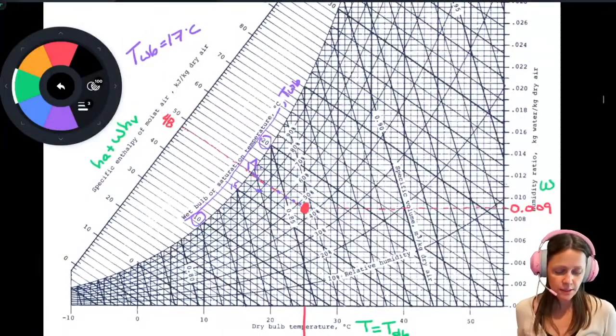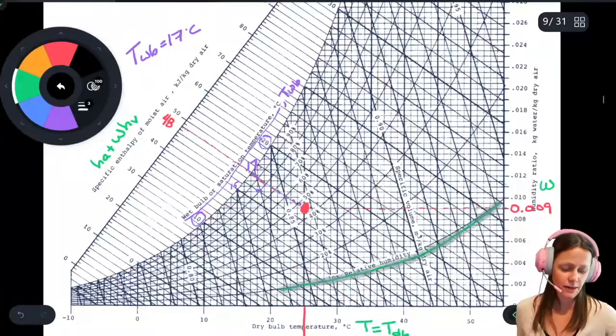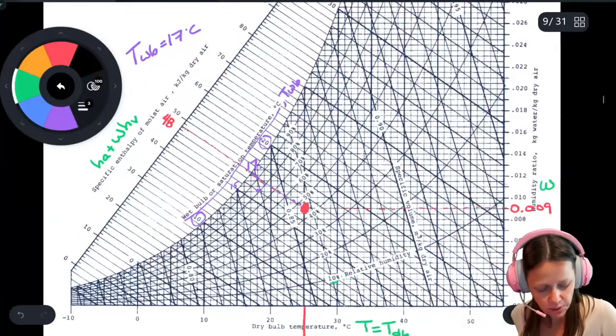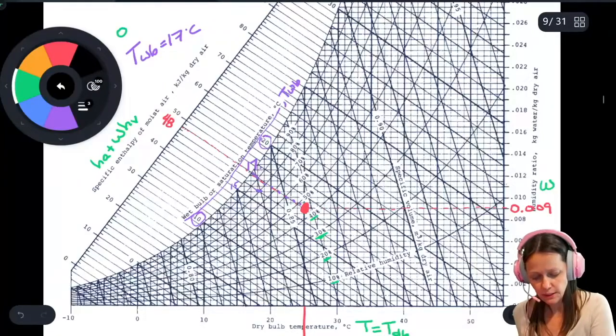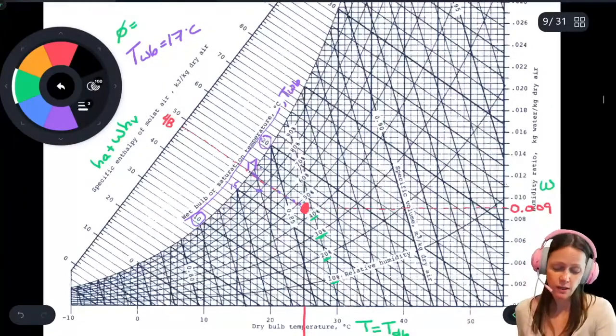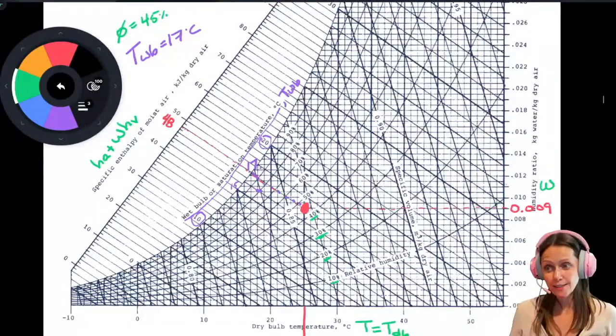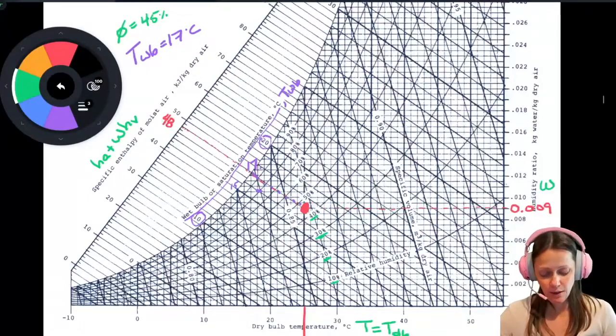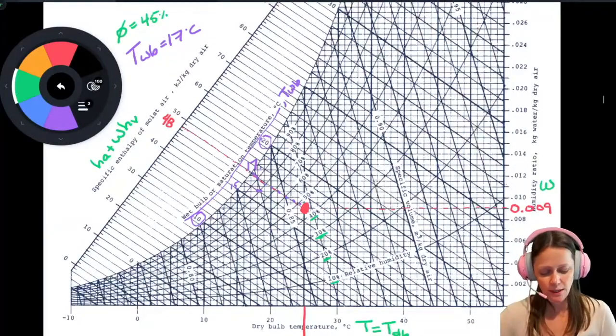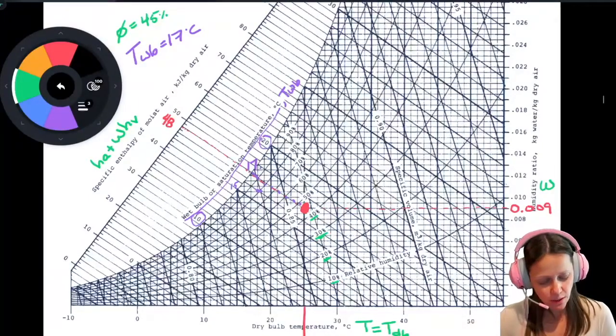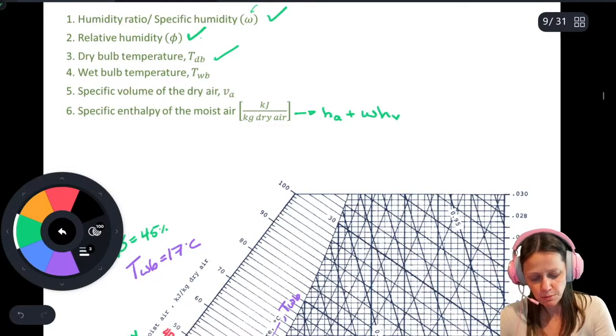The lines of relative humidity sort of curve upward — you've got 10%, 20%, 30%, 40%, and so on. For our point at 25 degrees Celsius, it's between 40 and 50%, so I might say about 45% relative humidity. Since you're reading off a chart or graph, there is going to be some variability between answers — that's okay. We've now covered relative humidity, dry bulb temperature, and wet bulb temperature.